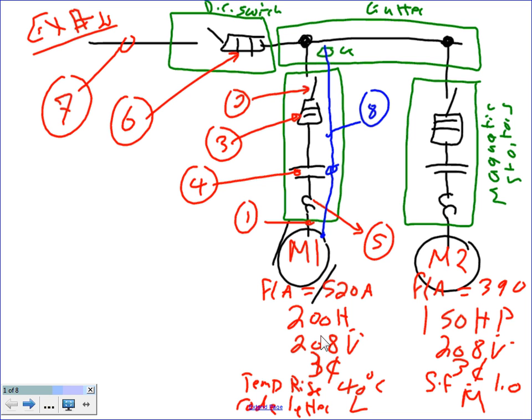overload. So if you put a fused disconnect, a contactor, and an overload, the combo, guys, they call it a magnetic starter, a combination. They call this one a magnetic starter disconnect fuse combination. The green color indicates a box, a physical mechanical size of a box. These are 4 different entities, the green things.